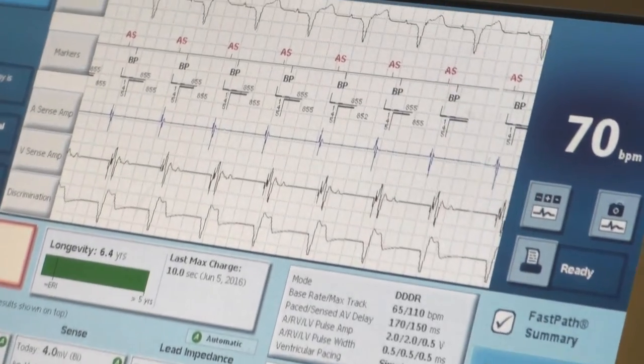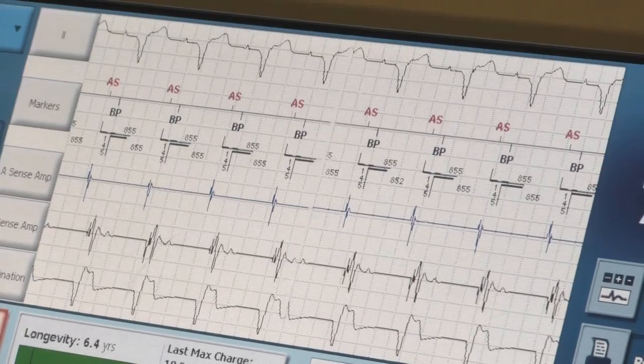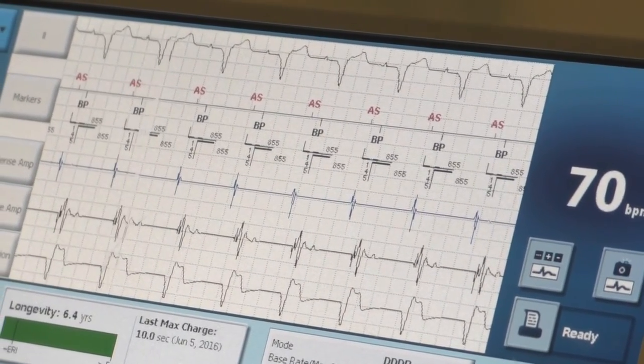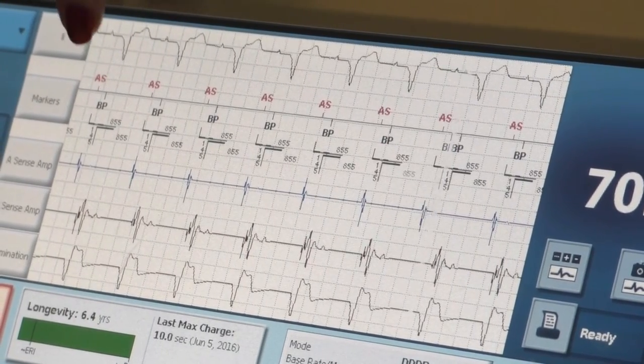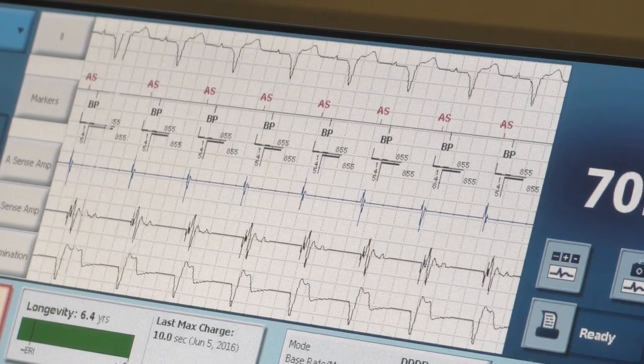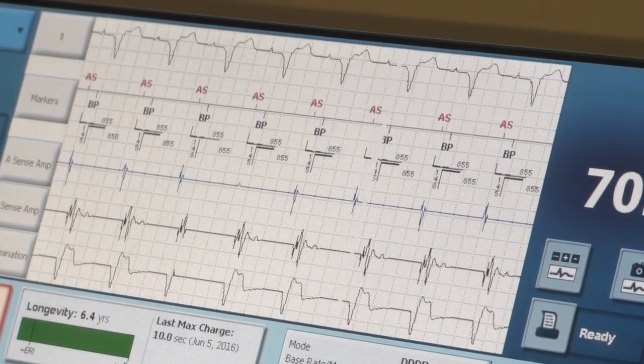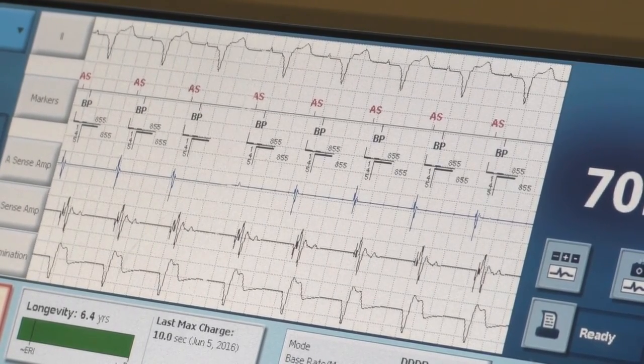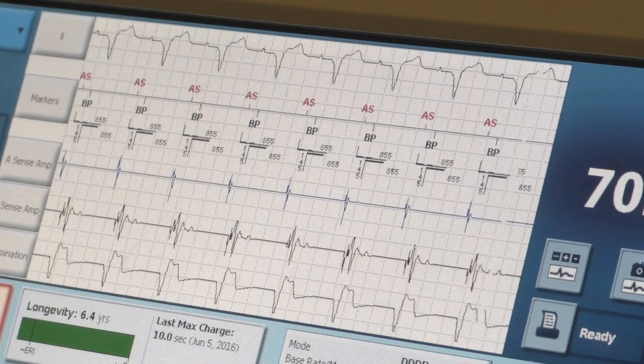Since it's a demo, it didn't change the morphology like it would in a real patient. But it's both the pacing rhythm and the actual rhythm. See how it's pink at the top? It's A-sense and V-pacing. The BiV pacemaker portion is tracking off of the sinus rhythm — sinus rhythm is at 70, and we're force pacing in the RV and LV.